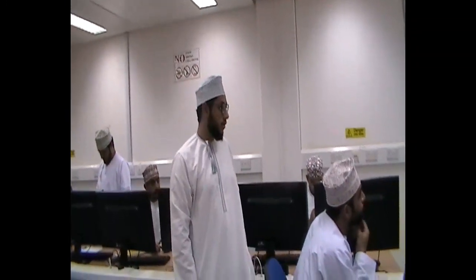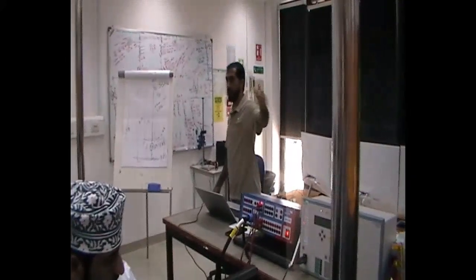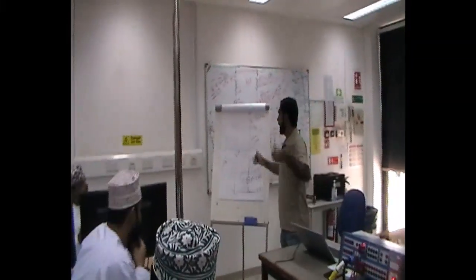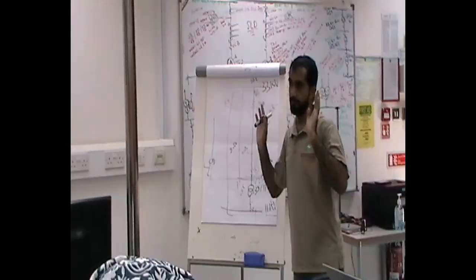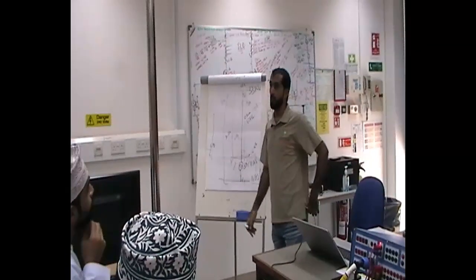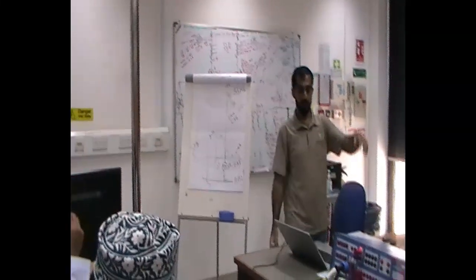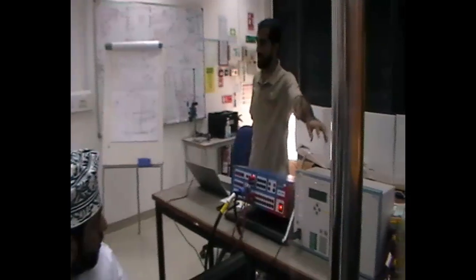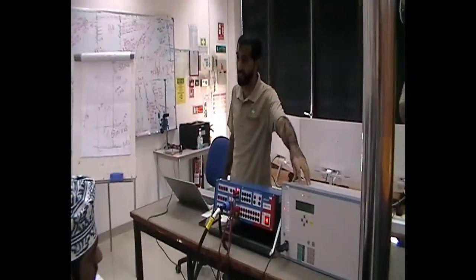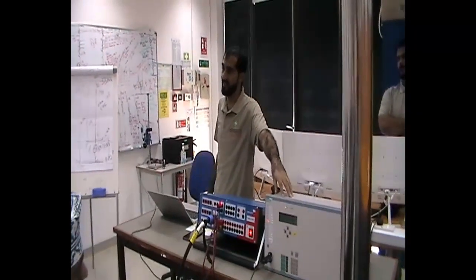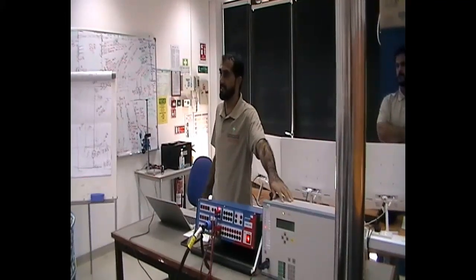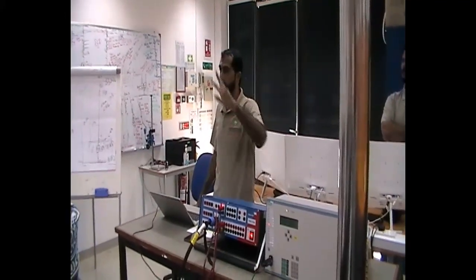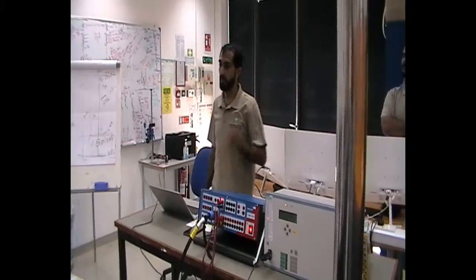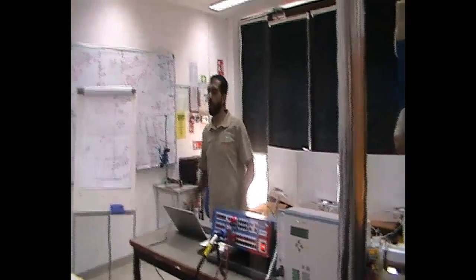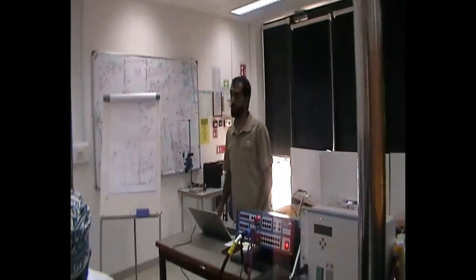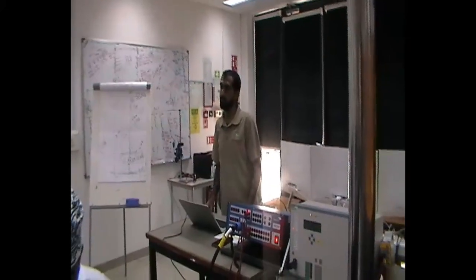No, basically if I am having distance relay as main protection, I will have another overcurrent relay. I could, but again, the cost for a relay that has distance and differential would be higher than a normal overcurrent relay. It's nonsense cost-wise. But then, like in the video, they would have two relays, both main, the same. In high voltage, they have two relays also. But it depends. We have distribution here.